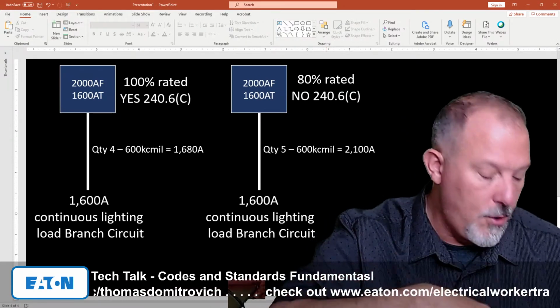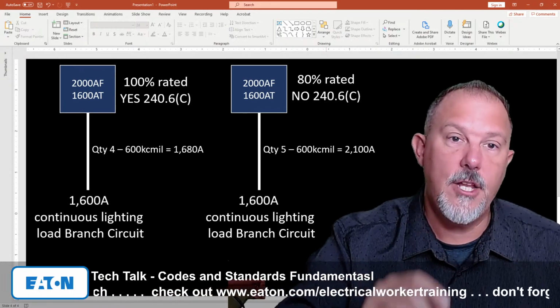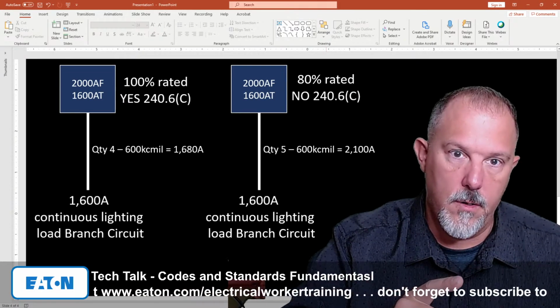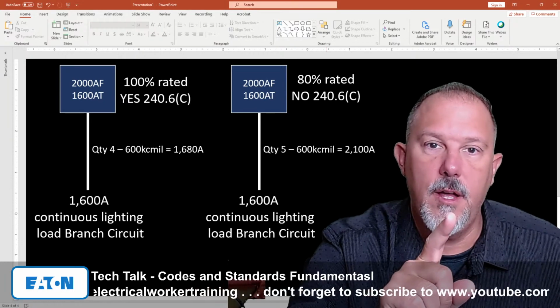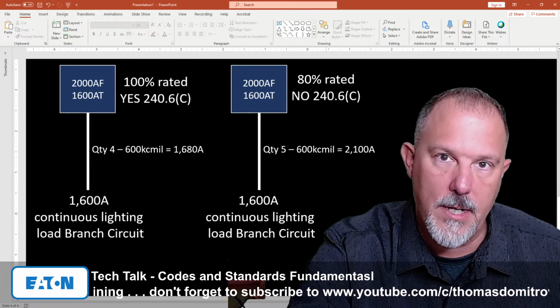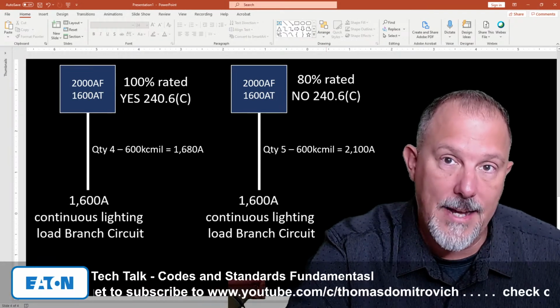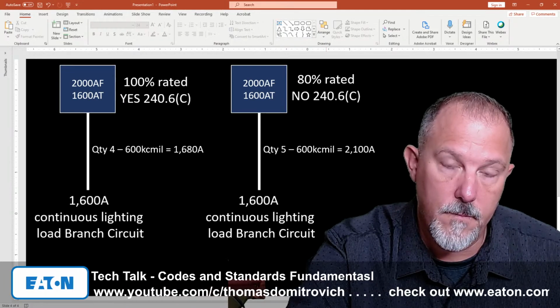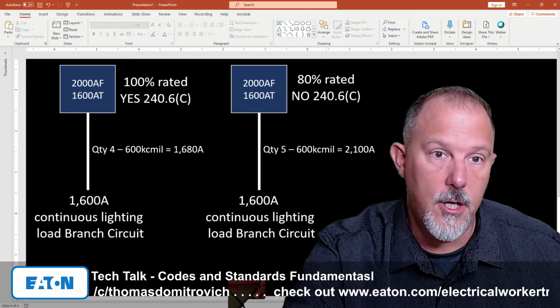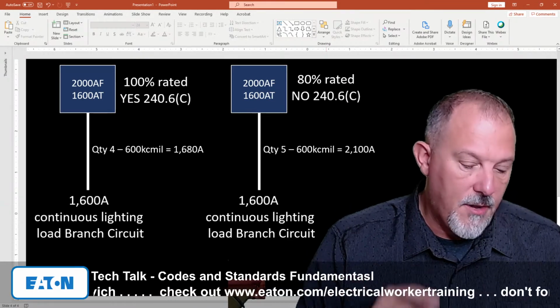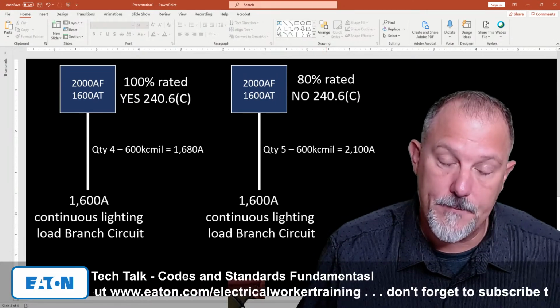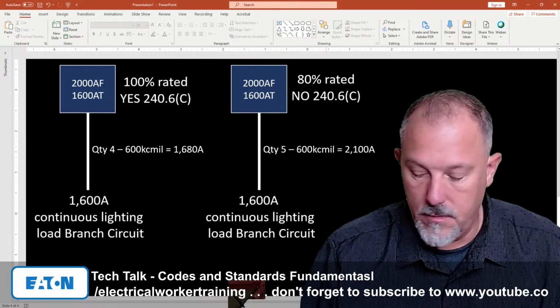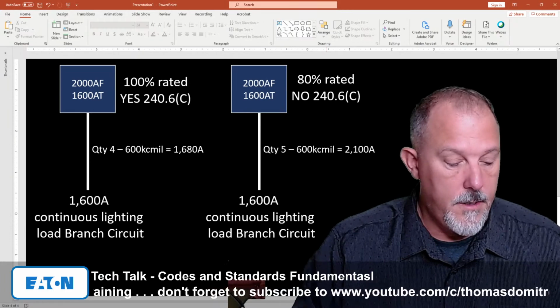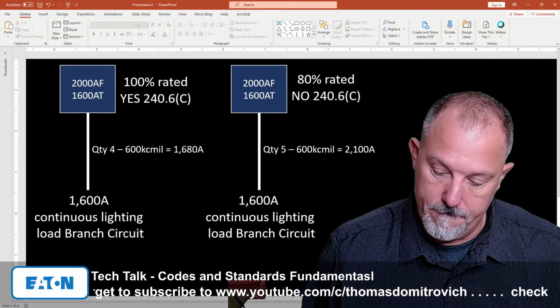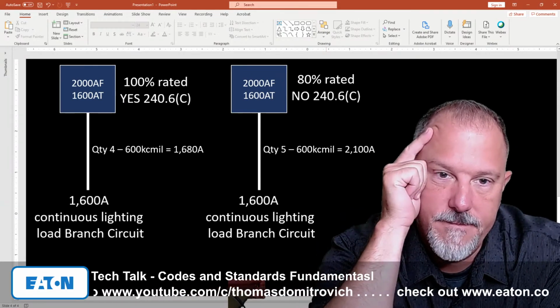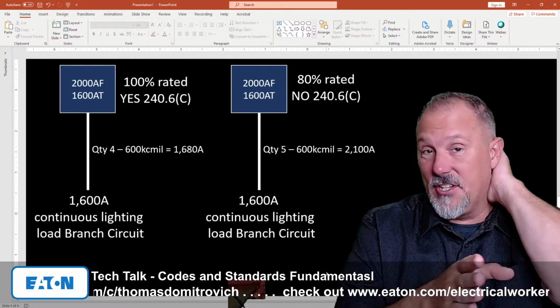And what you'll recognize there is that 215.3 makes sure that you do not have more current on a conductor than 80% of the rating of the conductor on that breaker, unless you have a 100% rated overcurrent device in a 100% rated enclosure. Those are the two key sections. I'm going to say them again, 215.3 and 210.20(A). Now, what about services? I was talking to Mr. John McCamish this morning, and I asked about this question. And what he pointed out, and he concurs with this as well.